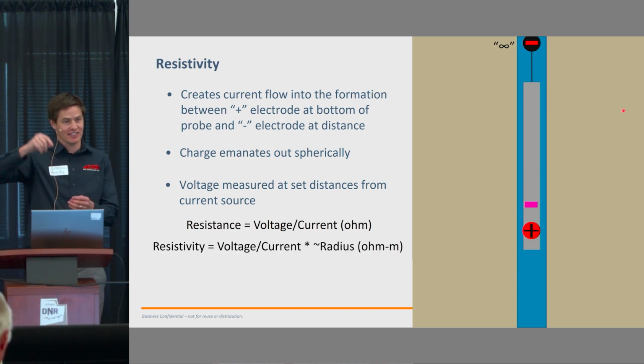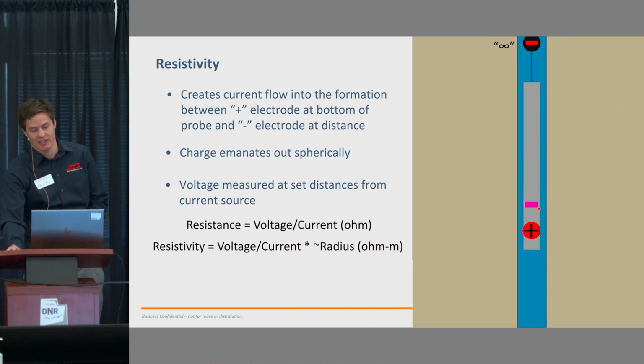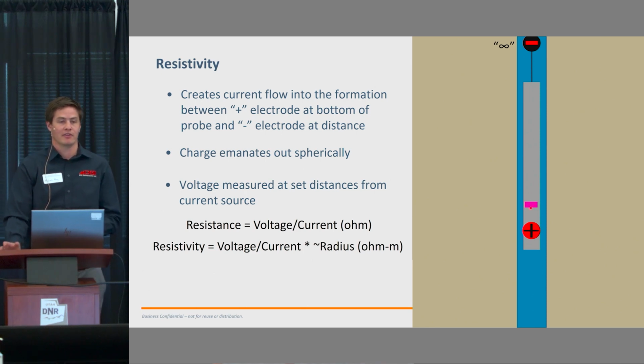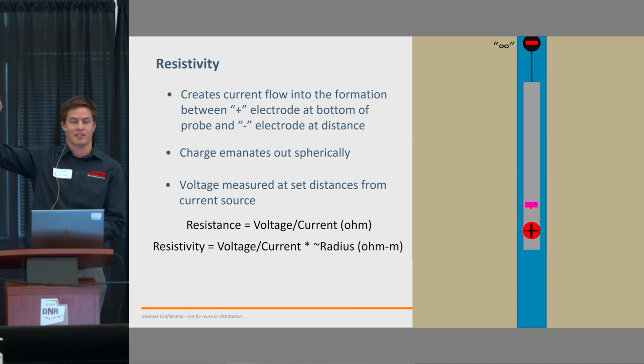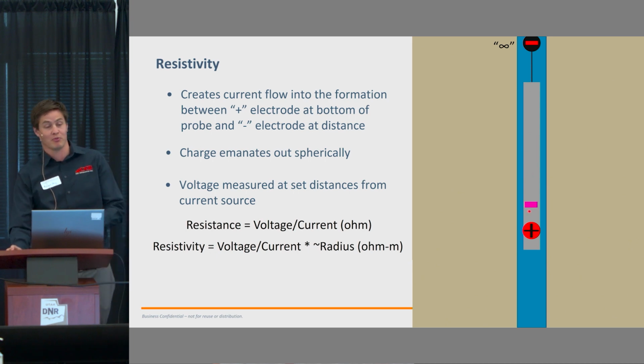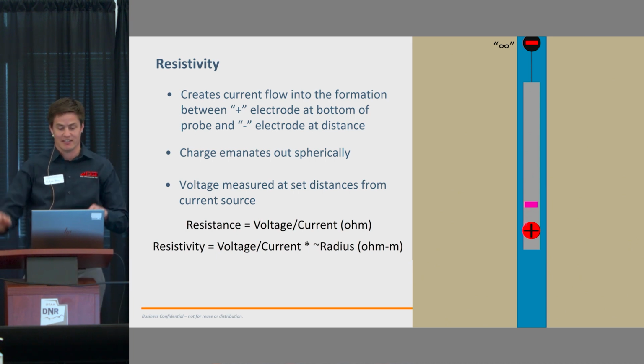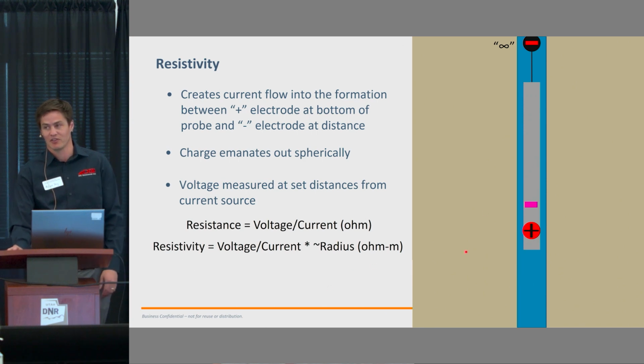So to account for the distance you put the voltmeter: if you move it up, it's lower voltage, so you'll get a lower resistance. All you do is multiply the resistance you measure by the distance between the probes. So if you move this voltmeter anywhere on the probe, it'll have lower voltage but a higher distance, and they even out—you'll measure the same resistivity. Multiplying resistance times distance gives ohms times meters, so the units for resistivity are ohm meters.